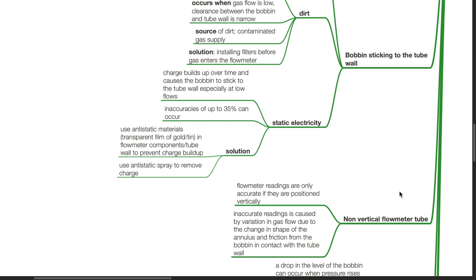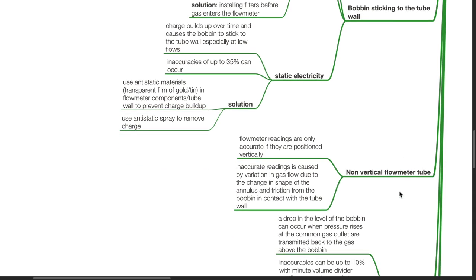Solution: Use anti-static materials such as transparent film of gold or tin in the flow meter components or tube wall to prevent charge build up and use anti-static spray to remove charge.